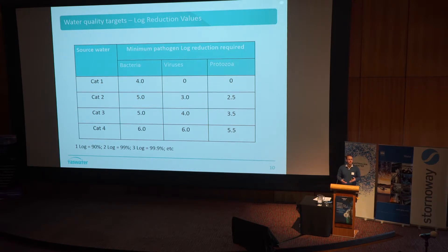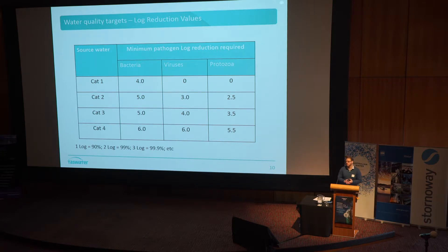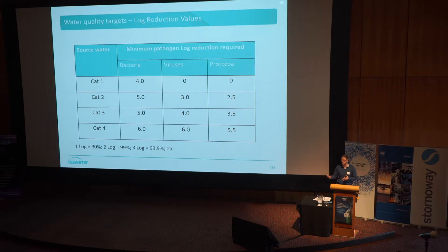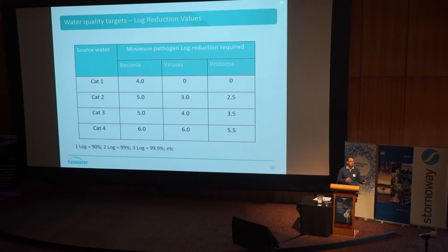In a category one catchment, you're basically only worried about bacteria — you need to remove four log of bacteria. In category four, you've got all the inputs: viruses, bacteria, and protozoa at fairly high concentrations, so you need higher log removals. For those not familiar with log removals: one log removal is 90% removal of what you had in the influent, two log is 99%, three log is 99.9%, and so forth.